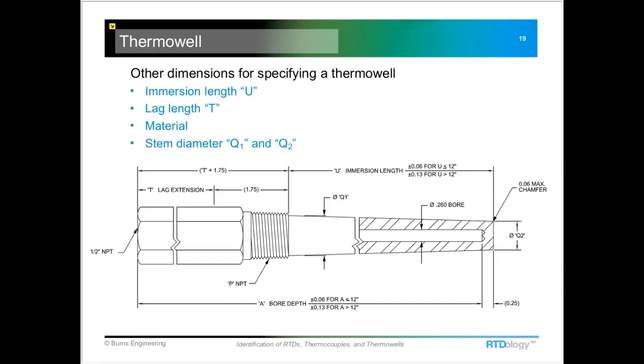Some of the other dimensions you'll see — if you need to specify a replacement thermowell — include the immersion length, which is the U dimension. That's the distance from the end of the threads down to the tip of the well, and then again the bore depth.